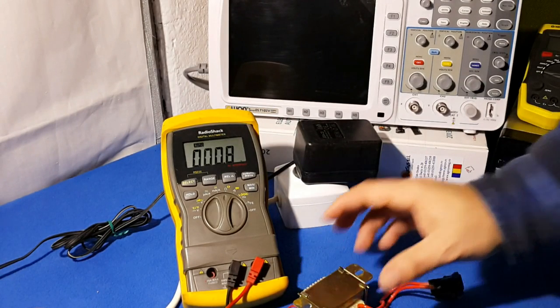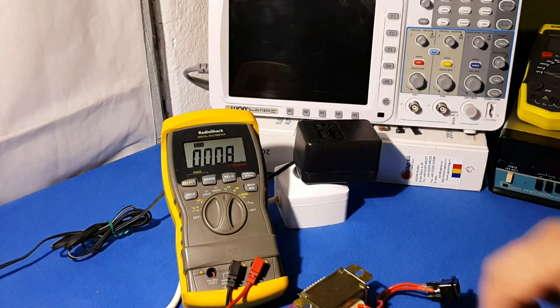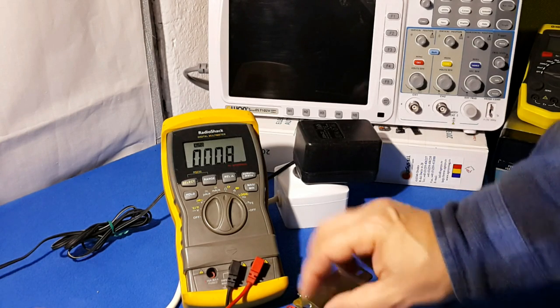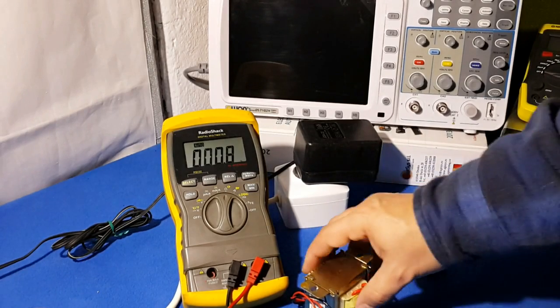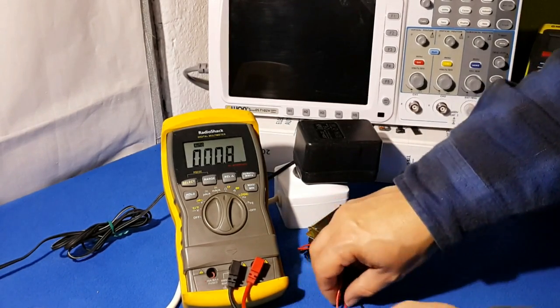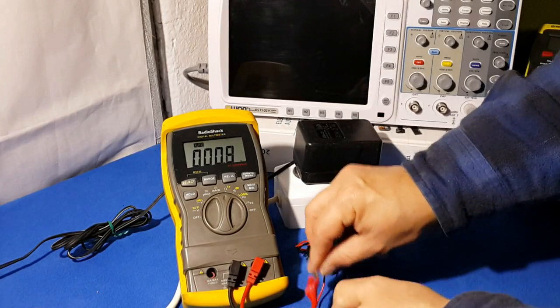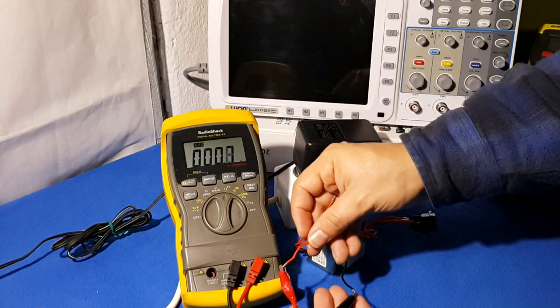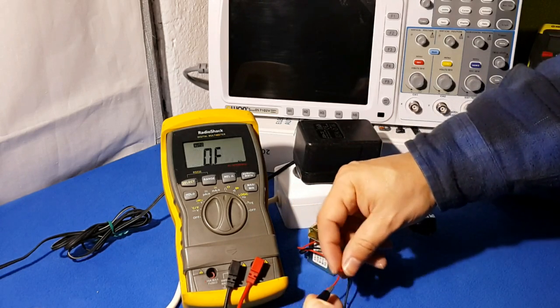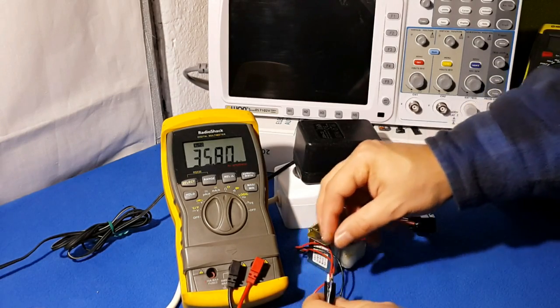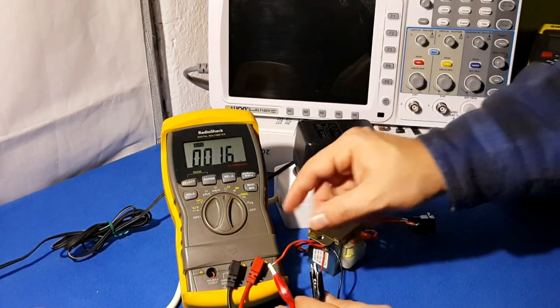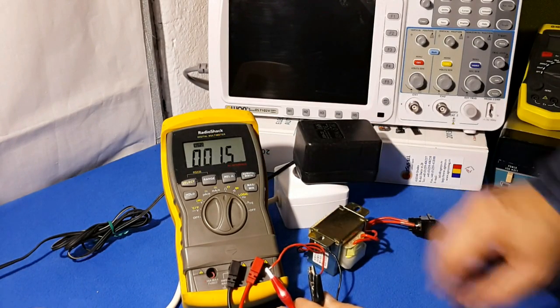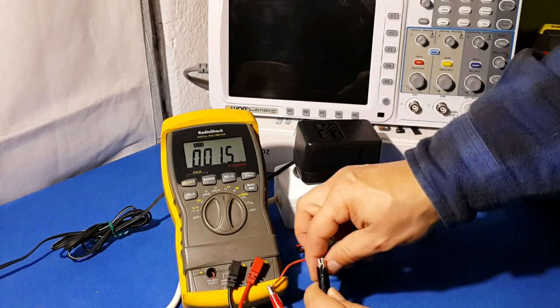In the secondary, we're expecting very low resistance. Because this transformer is a center tap, I have two windings. I will move the transformer here—I have two windings. So the other one should be like this. But if I remove the center and I use the long way with both windings, I will get a little bit more resistance. As I said, if you get an open circuit, OL, overload, that means the wire is broken inside.